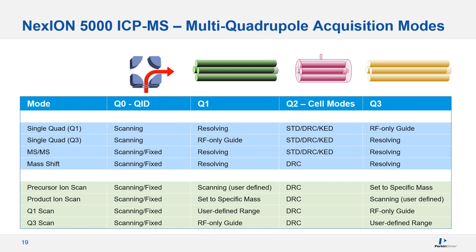With the Nexion 5000's multiple quadrupole acquisition modes, not only can you operate in single quadrupole mode, but you can also run it in MS-MS mode and mass shift mode. There is also the ability to do ion scans — both precursor and product ion scans — before and after the reaction cell to see what is being formed, which is useful when developing methods.